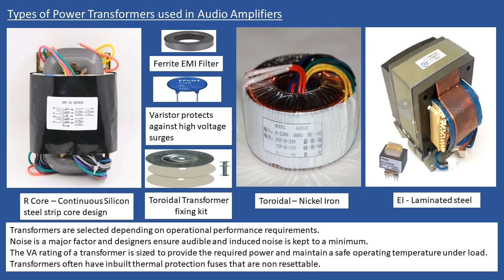So you may have fixing bolts that come into the bottom, or the base plate could be threaded, or you may have what we call a top hat type transformer. This is where it has like an outer cage which goes around, and then it's sort of clamped underneath, but again held in place either with 2 bolts or 4 bolts.